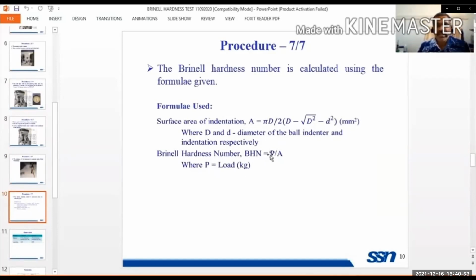So the Brinell hardness number is load divided by area. Area you can substitute from here in millimeter, and load in kg. So it will give you a number. It doesn't have any unit. It is just a number, the Brinell hardness number. That will give the indication of hardness.